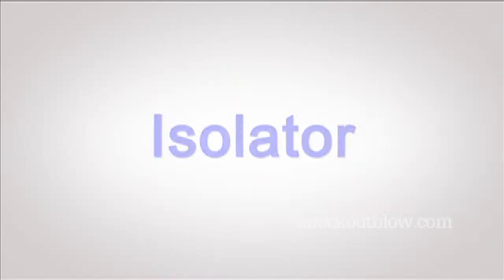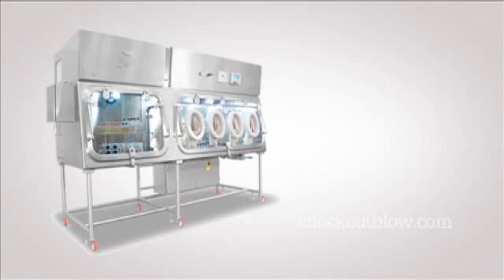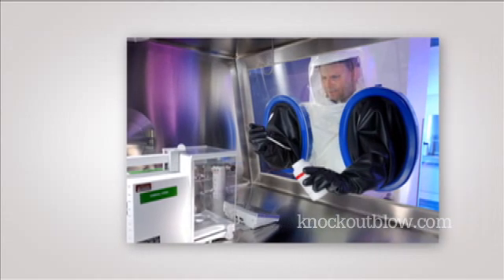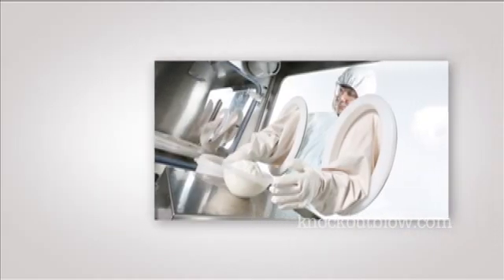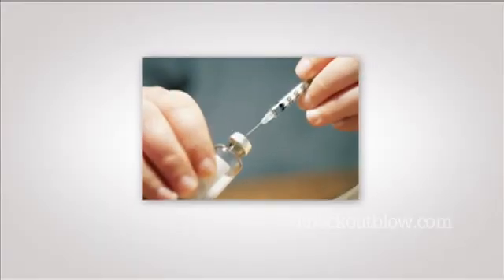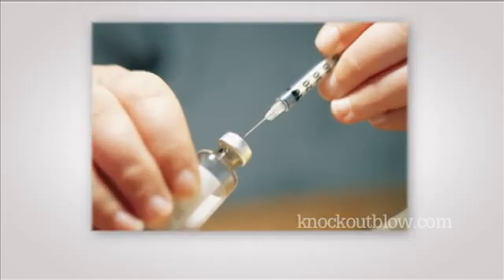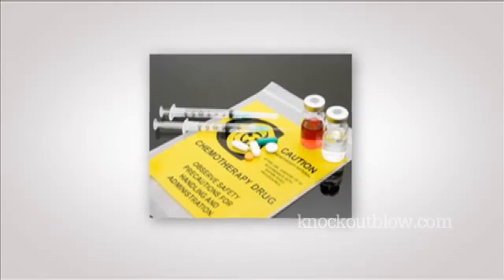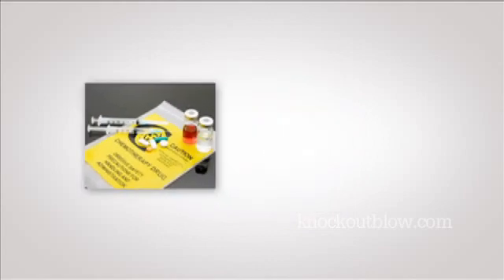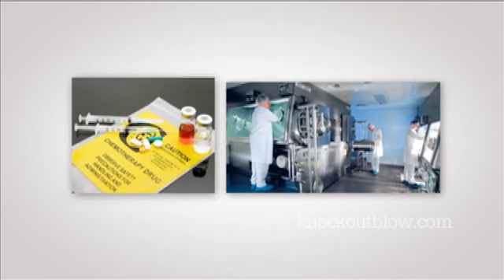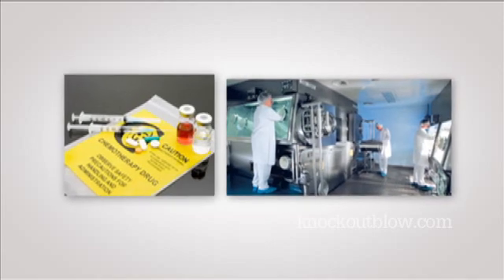Isolator: An isolator is a type of enclosed ventilation system that has physical barriers. Internally, it provides a workspace which is separated from the surrounding environment. There are positive and negative pressure isolators. Positive pressure isolators can be used for the aseptic preparation of pharmaceutical products, while negative pressure isolators are used to protect the operator from hazardous materials such as cytotoxic preparation.